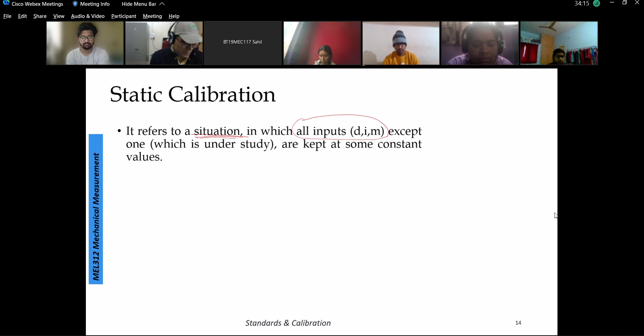For example, I want to know the length of this piece compared to a standard, maybe a local standard I'm using. So I find the distance between the two points, and then compare this measured unit with the standard scale. Except the length under measurement, all other inputs are kept constant, say temperature, pressure, and everything else in the room, so that only the variation in the displayed output of the measurement system is checked.